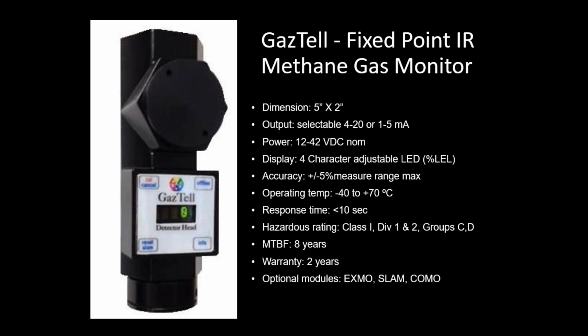As far as some of the other things, I don't want to call it a me too, but one of the things I always get concerned about is people looking too much into the accuracy and the response time. Everybody has to meet Factory Mutual on a lot of these products, and therefore, although somebody might claim a second or two quicker response or a percentage point more accurate or repeatability, we're probably all in the same range. It's just how we choose to describe our accuracy and our response times that makes it different on paper, but actually they're all the same. And that's important because we often have customers say, well, I like yours, but your competitor is 4% accurate and you claim 5%. Well, that should be meaningless when you're talking about gas detection, because what's more important is repeatability and accuracy as far as giving you an alarm when a gas leak happens.